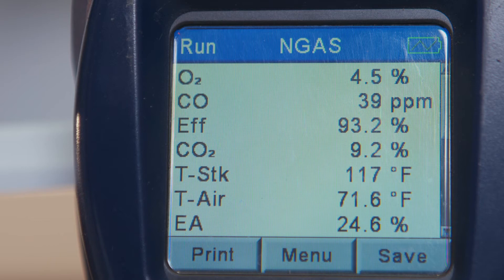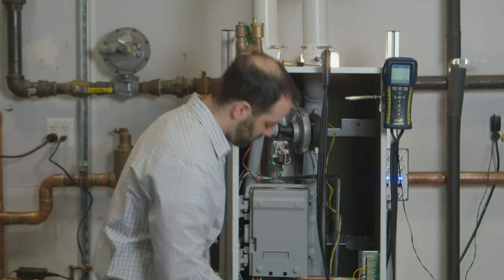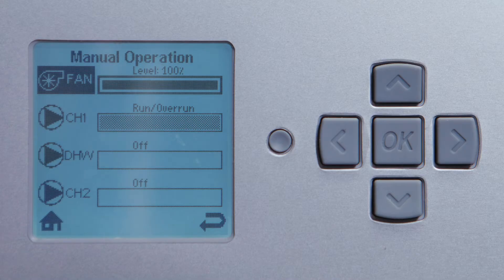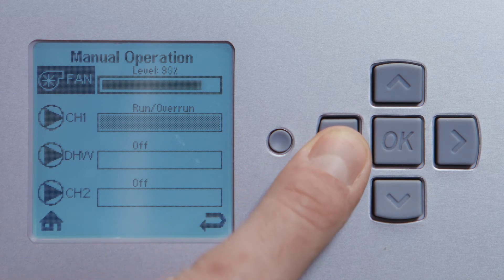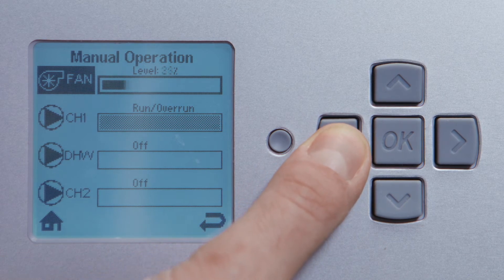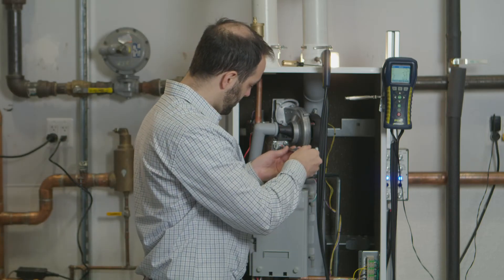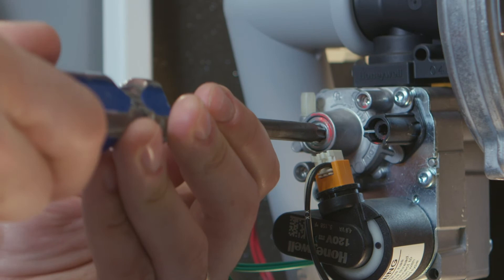The next step is to go to low fire. On the fan icon in the manual operation, press left and drop the percentage down all the way to 1%. We want to remove the offset cap, so use the T40 screwdriver to remove the cap.